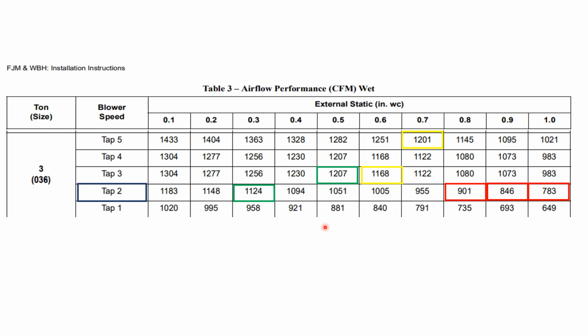So keep in mind, our units are not making air. We're moving air from one end of the house to the next. So when we talk about setting capacity, this is what we're talking about. If you move this pin to tap 3, but you don't check static, you could easily be in these danger ranges that's going to cause a compressor to go out in 2 years to 3 years to 6 months to 6 weeks. I've seen compressors last 6 weeks and go out.